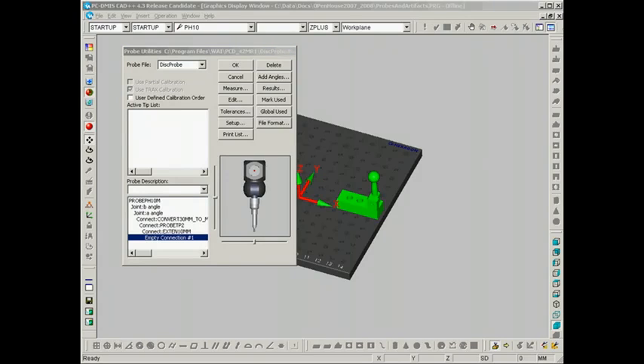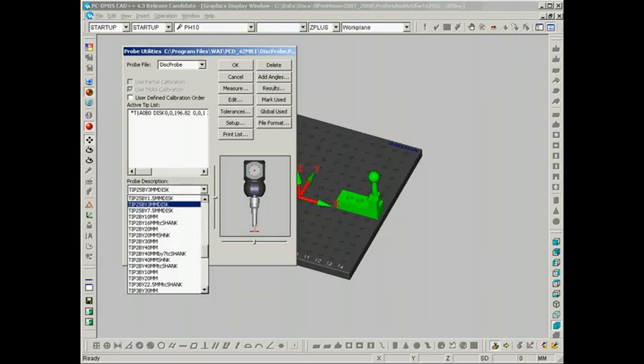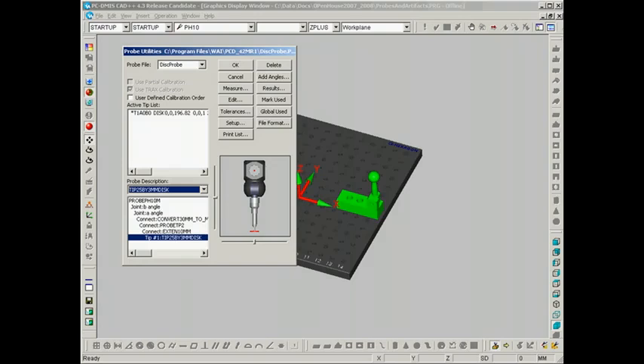What you want to do next is take the disc stylus that you plan on using and just quickly have a look at it with a caliper so you can determine the diameter and its thickness, because that's how they're listed inside of the hardware description. So what you want to do next is scroll down through the list of the hardware until you find the disc that you're going to use. Now, my favorite disc is the 25 by 3 millimeter disc, because it's slightly larger in diameter than the body of the TP2. So this allows me to get fairly deep into bores and measure O-ring grooves and things like that.